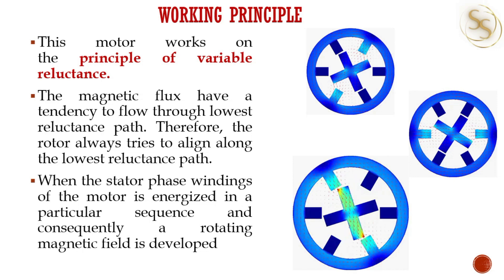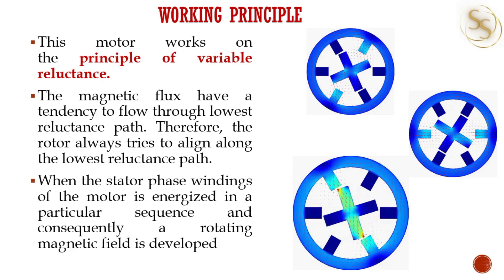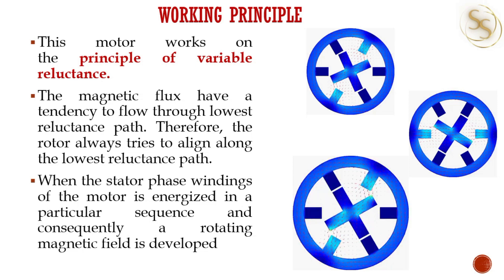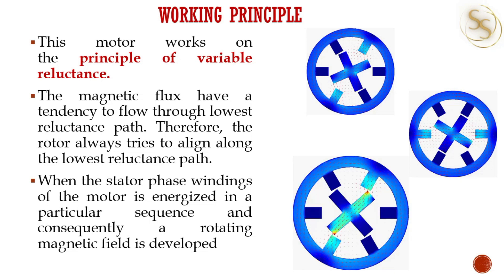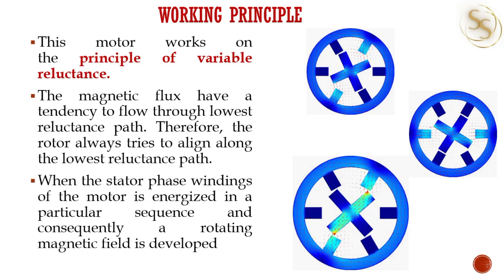Whenever a stator winding is energized, it will produce a magnetic field and the rotor will tend to align to the stator so that the flux path — or the reluctance path — will become minimum. When the stator windings are energized in a sequence, consequently, the rotor will continuously rotate in order to maintain the lowest reluctance path.